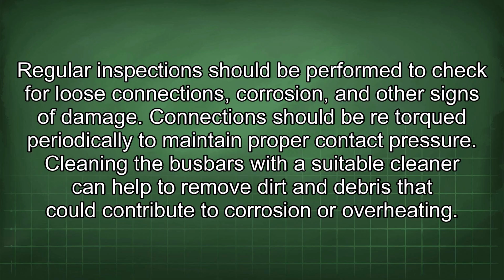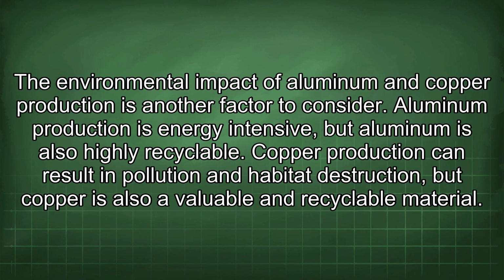Regular inspections should be performed to check for loose connections, corrosion, and other signs of damage. Connections should be retorqued periodically to maintain proper contact pressure. Cleaning the busbars with a suitable cleaner can help to remove dirt and debris that could contribute to corrosion or overheating. The environmental impact of aluminum and copper production is another factor to consider.